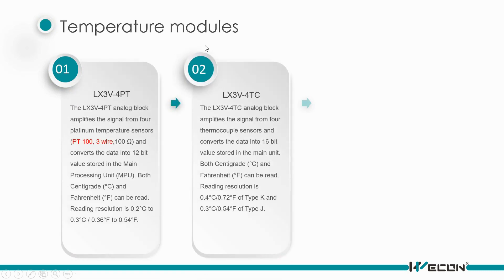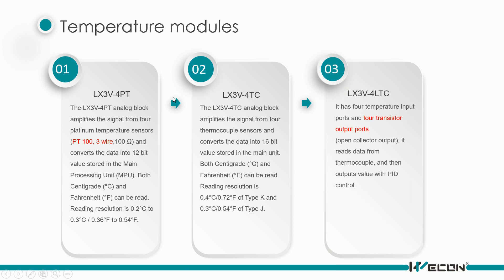For the temperature modules, we have 4PT, 4TC, and 4LTC. The 4PT must connect with a PT100 sensor — the sensor needs to be a 3-wire sensor. The 4TC works with a thermocouple. The difference between 4TC and 4LTC is that 4LTC can also output high-speed pulses, which are used for PID control.